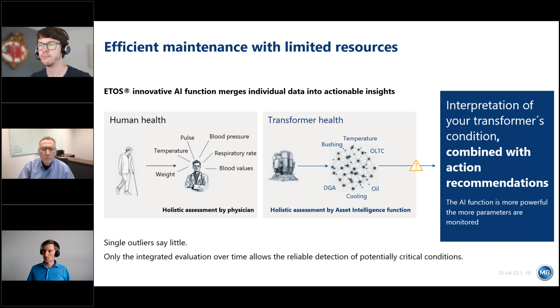The first example is a very basic one, which probably all of you would be able to assume. Let's assume there is a transformer. We got a Buchholz relay warning, so the first warning level has been reached. At the same time, we have a DGA sensor installed on this transformer, and we see a lot of H2 generated. So within asset intelligence you would see several diagnostics that might be true there, but you see the first one, shorted winding, as the most probable reason. This is what the user of this function would see.